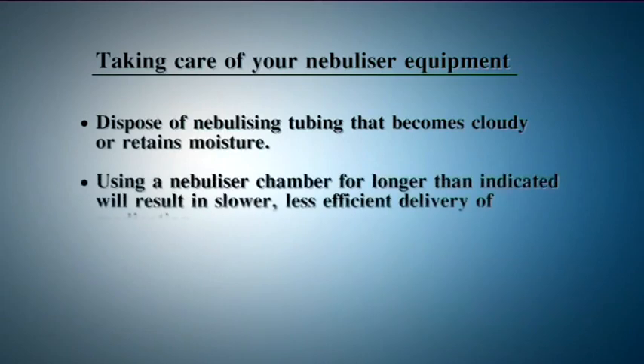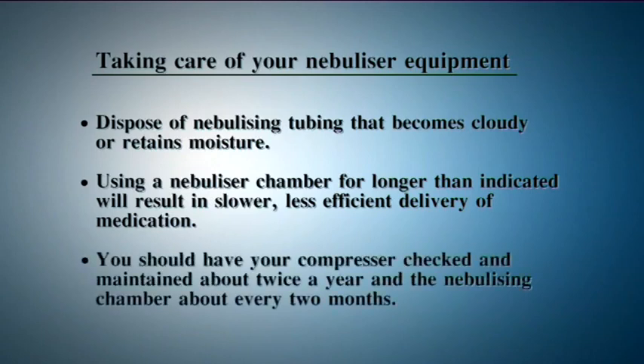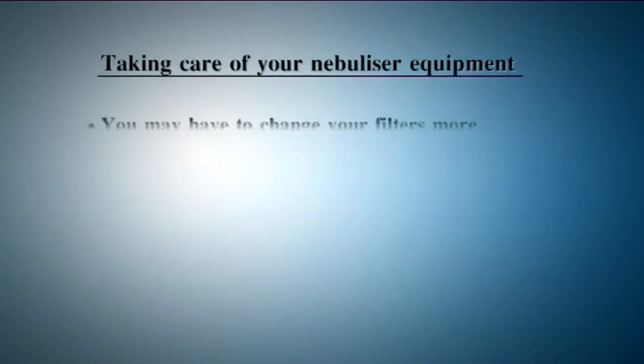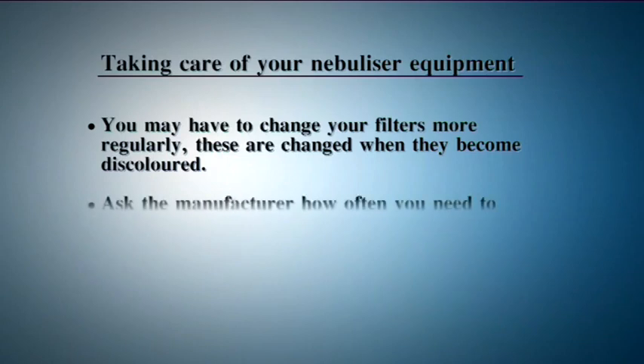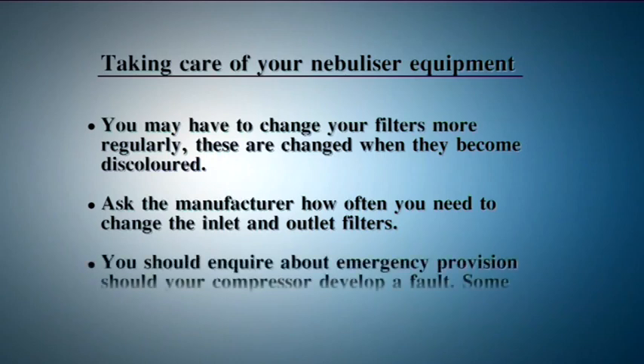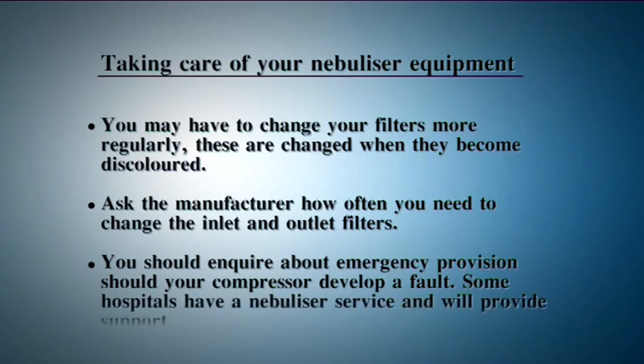Taking care of your nebuliser equipment. Dispose of nebulising tubing that becomes cloudy or retains moisture. Using a nebuliser chamber for longer than indicated will result in slower, less efficient delivery of medication. You should have your compressor checked and maintained about twice a year and the nebulising chamber about every two months. You may have to change your filters more regularly — these are changed when they become discoloured. Ask the manufacturer how often you need to change the inlet and outlet filters. You should inquire about emergency provision should your compressor develop a fault. Some hospitals have a nebuliser service and will provide support.